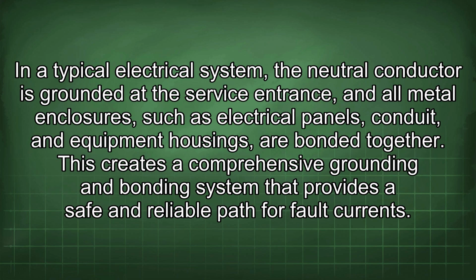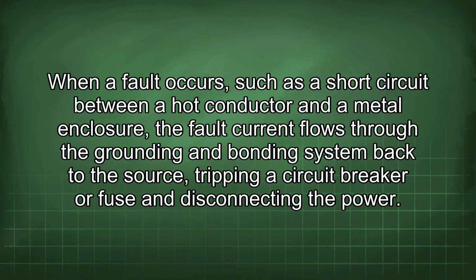In a typical electrical system, the neutral conductor is grounded at the service entrance, and all metal enclosures, such as electrical panels, conduit, and equipment housings, are bonded together. This creates a comprehensive grounding and bonding system that provides a safe and reliable path for fault currents. When a fault occurs, such as a short circuit between a hot conductor and a metal enclosure, the fault current flows through the grounding and bonding system back to the source, tripping a circuit breaker or fuse and disconnecting the power.